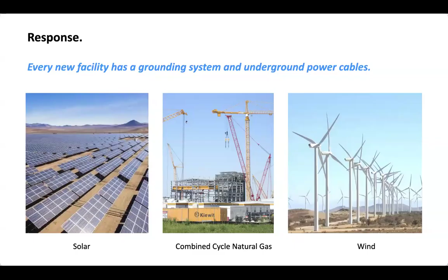And so let's talk about resistivity. Grounding grids. Every electrical component of a power system needs to be grounded so that no one gets electrocuted if a problem occurs. And since power systems cannot be shut down instantaneously, electric current is diverted into the earth through the grounding grid. And a grounding grid is literally a mesh of buried copper wires that dissipates electric current into the earth across a large area. Schematically, it underlies the whole power plant footprint, and they're laid in by trenching, just like that you see on the right.